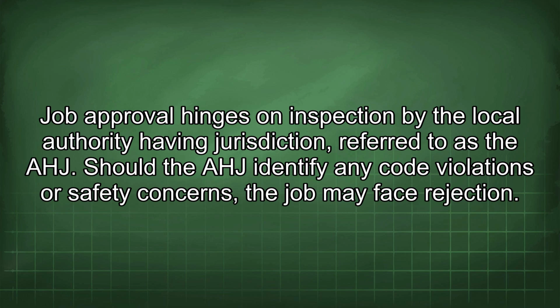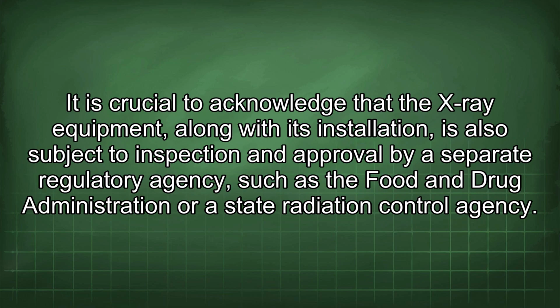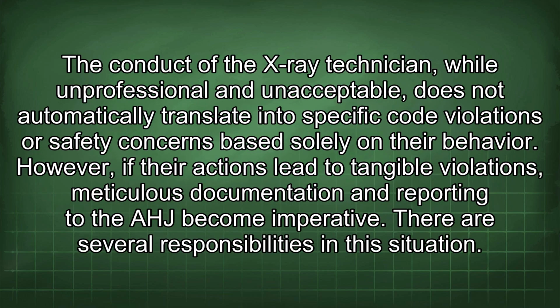Should the AHJ identify any code violations or safety concerns, the job may face rejection. It is crucial to acknowledge that the X-ray equipment, along with its installation, is also subject to inspection and approval by a separate regulatory agency, such as the Food and Drug Administration or a state radiation control agency. The conduct of the X-ray technician, while unprofessional and unacceptable, does not automatically translate into specific code violations or safety concerns based solely on their behavior. However, if their actions lead to tangible violations, meticulous documentation and reporting to the AHJ become imperative.